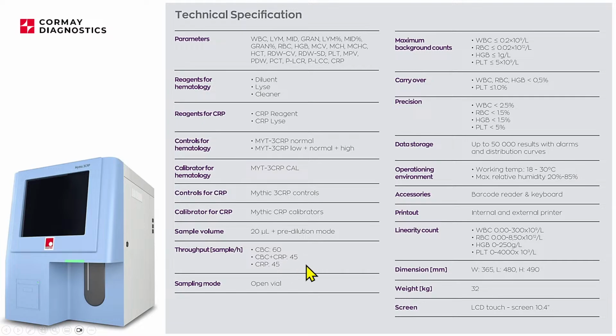For CRP, we have slightly less, so it's 45 if we also use the CBC, and CRP is a limitation here, so 45 if we only use the CRP. Sampling mode, this is only open vial. There is no autoloader, so basically you need to mix the blood and present the blood to the analyzer, and the operator needs to do that and run the analysis.